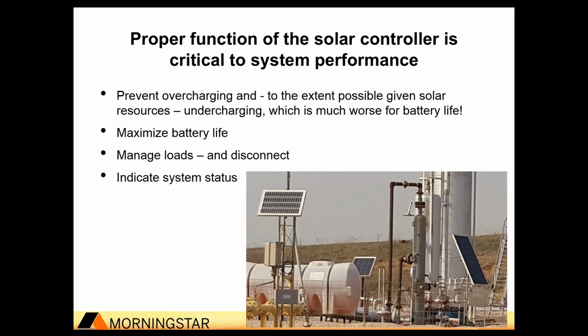Again, that low voltage disconnect of managing a load when the batteries are low is truly intended to be a fail-safe. A lot of times we get questions about being able to adjust the LVD set points on our equipment, and we'd say, of course, in the worst case scenario, you could always wire a load directly to a battery and risk a pretty substantial failure of that battery system if the system is not sized properly.